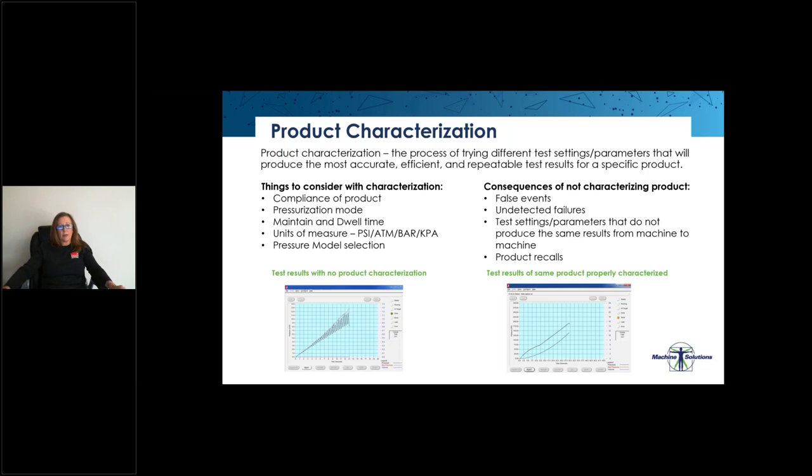I've talked a lot today about testing products and what parameters to use, which leads me to something that we call product characterization. Product characterization is the process of trying different test settings and parameters that will produce the most accurate, efficient, and repeatable test results for a specific product.